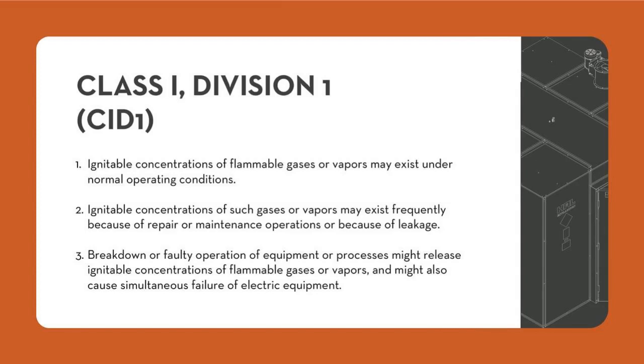So C1D1 is a rating, a classification, for a room. It's an electrical classification, so you have to have rated electrical equipment that is non-sparking. Generally, you will see an AHJ requiring you to house Class 1A solvents in a C1D1. An example of Class 1A would be pentane, butane, propane. For our example, we'll use butane. Butane is a vapor at room temperature. So if you're opening any of your vessels and you have butane escape, it's going to escape into your room as a vapor. Vapor is much more combustible than a liquid.